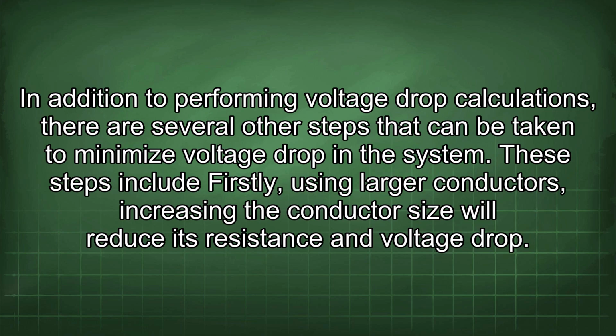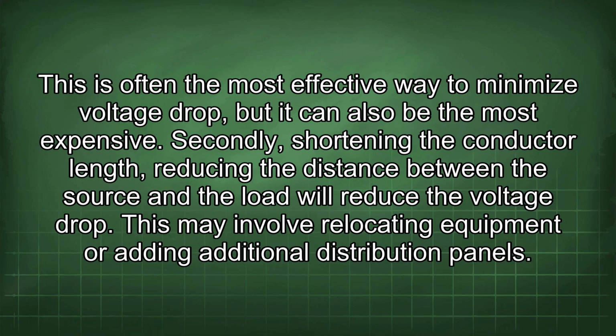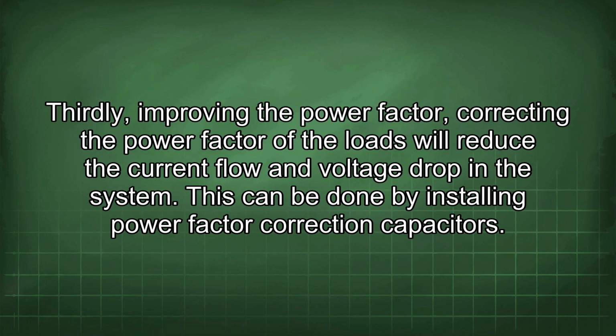These steps include, firstly, using larger conductors. Increasing the conductor size will reduce its resistance and voltage drop. This is often the most effective way to minimize voltage drop, but it can also be the most expensive. Secondly, shortening the conductor length. Reducing the distance between the source and the load will reduce the voltage drop. This may involve relocating equipment or adding additional distribution panels. Thirdly, improving the power factor. Correcting the power factor of the loads will reduce the current flow and voltage drop in the system. This can be done by installing power factor correction capacitors.